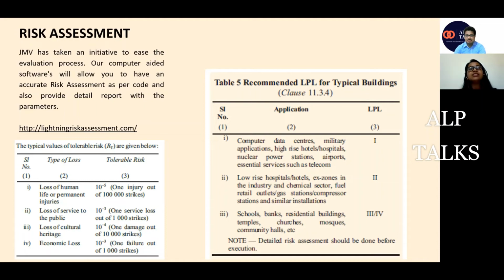Risk assessment is basically based on 4 types of losses: loss of human life, loss of services to the public, loss of cultural heritage, and economic loss. These 4 losses can happen if lightning strikes any structure, so the risk assessment calculation is done for these 4 losses, and tolerable values are given for them. If my calculated values come below the tolerable values, then I do not need a lightning protection system. But if the calculated values are higher than the tolerable risk, then I need to protect my system by installing the lightning protection system.